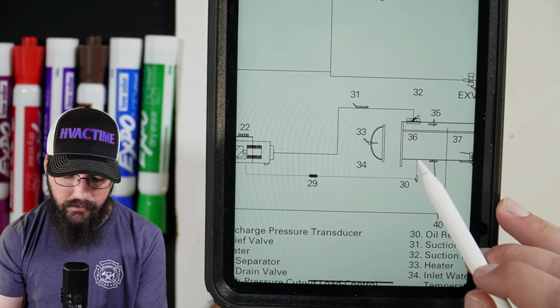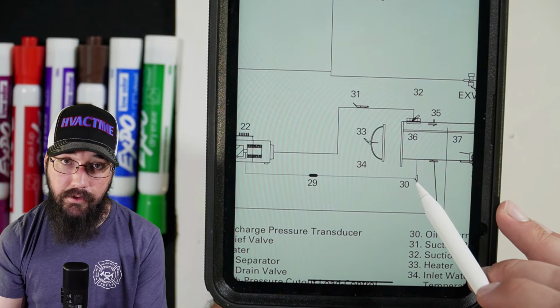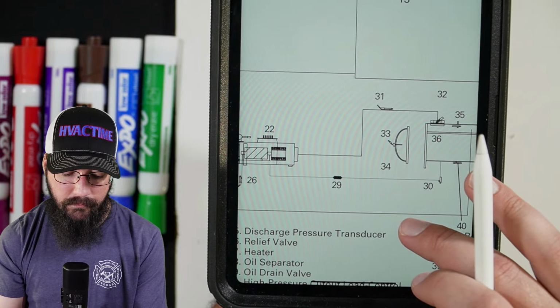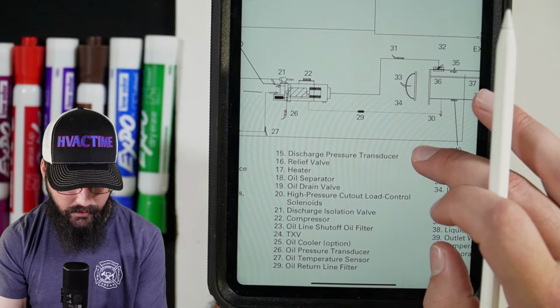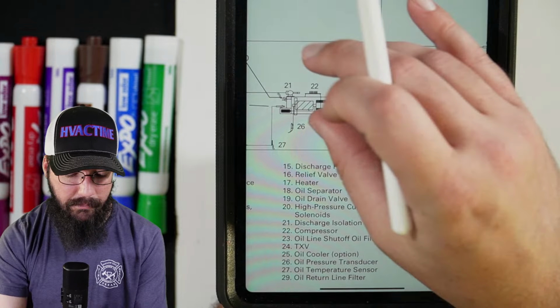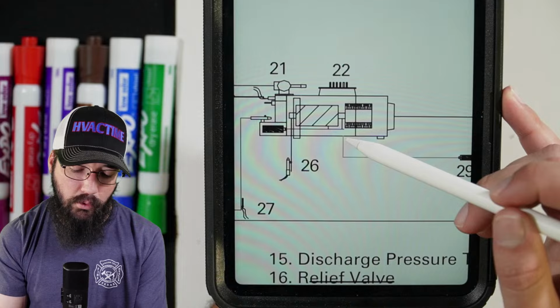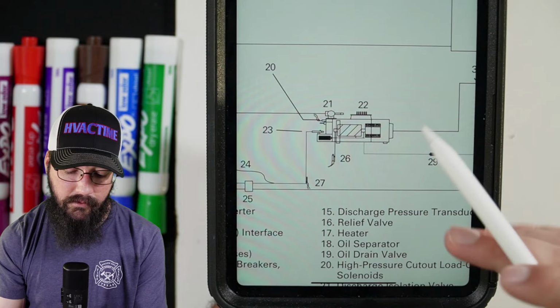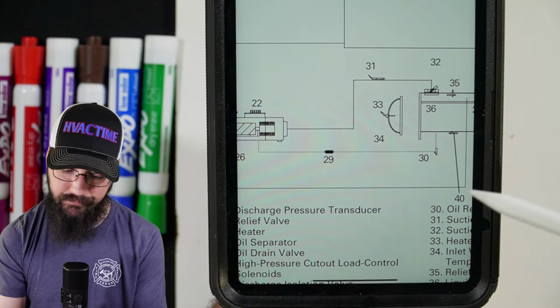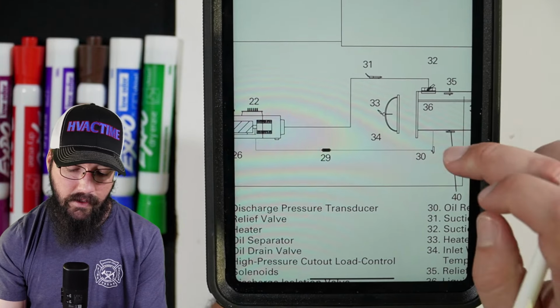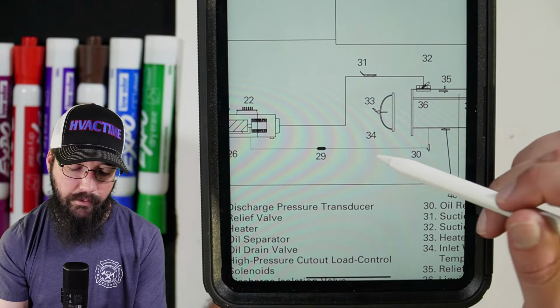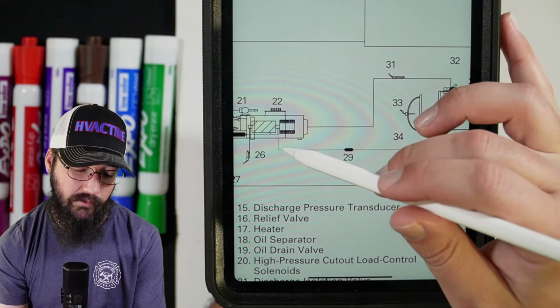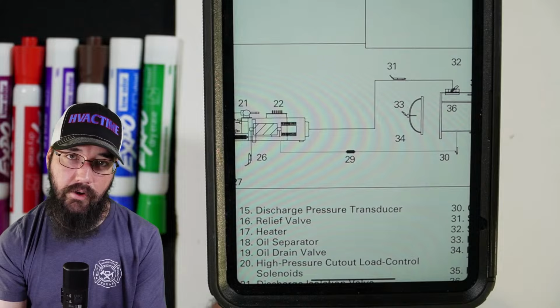Okay. So because of that, we can draw that oil off into our return line. This particular one I don't think uses an actual eductor. I believe it has a port in here that is metering that. So it's not literally drawing liquid refrigerant and dumping it straight into the compressor on this machine, because a lot of machines use actual eductors. This machine draws that refrigerant oil mixture off of the evaporator and sends it through a fixed orifice, if I'm not mistaken, into the compressor return. That flashes off the liquid refrigerant, the oil stays oil, and that's how we're able to get that oil back.